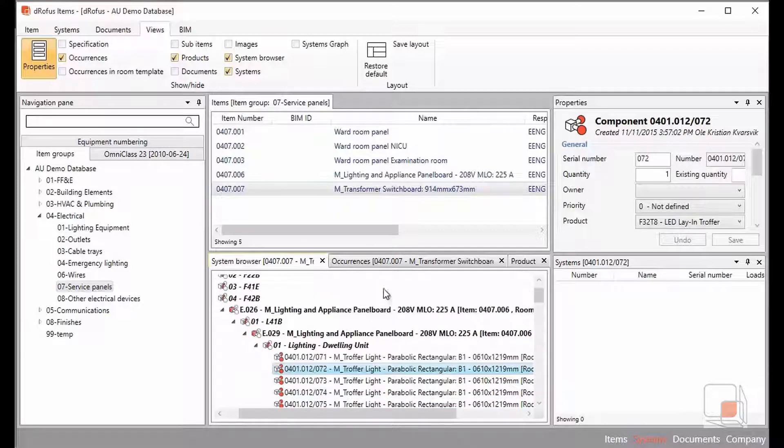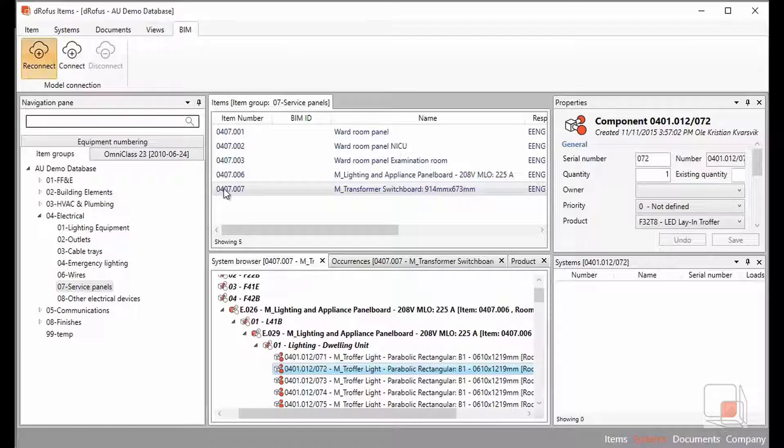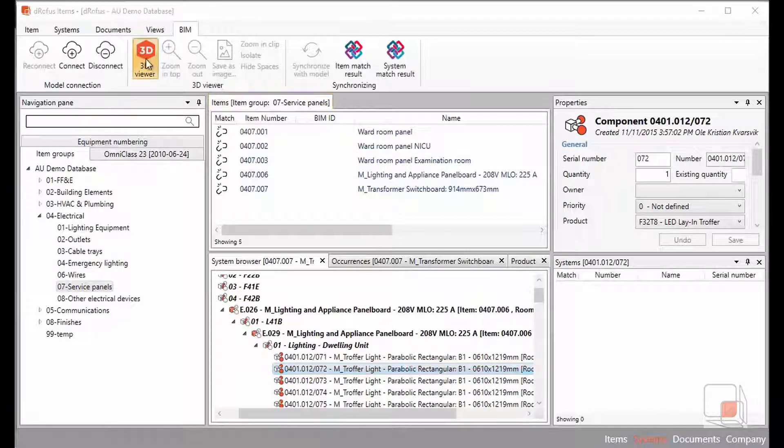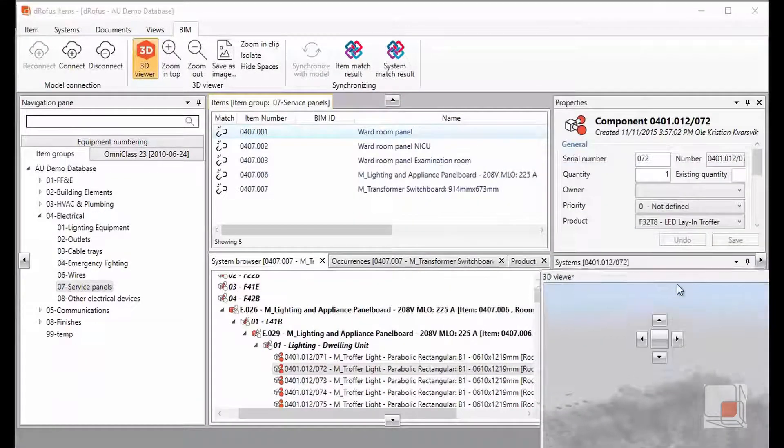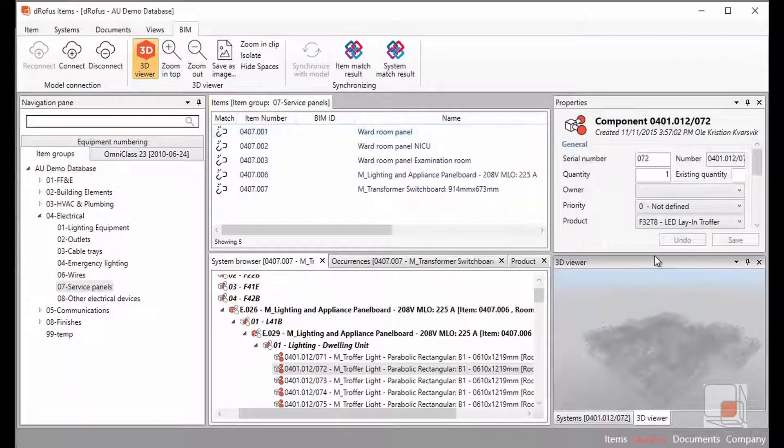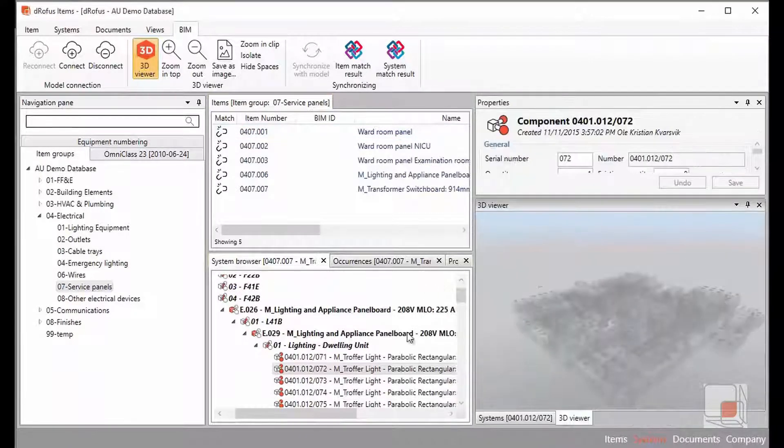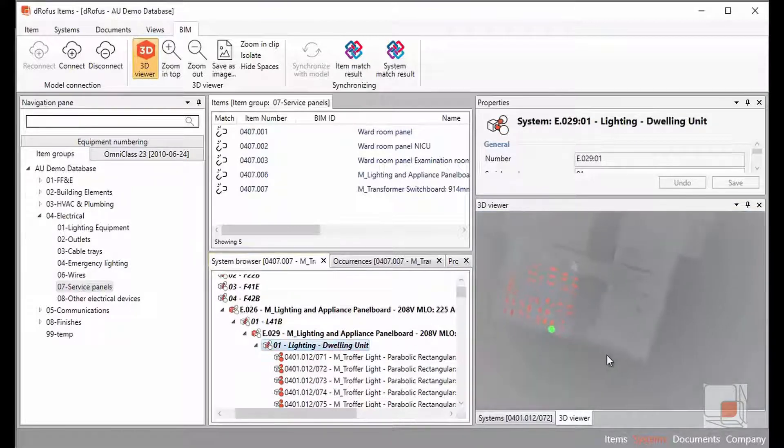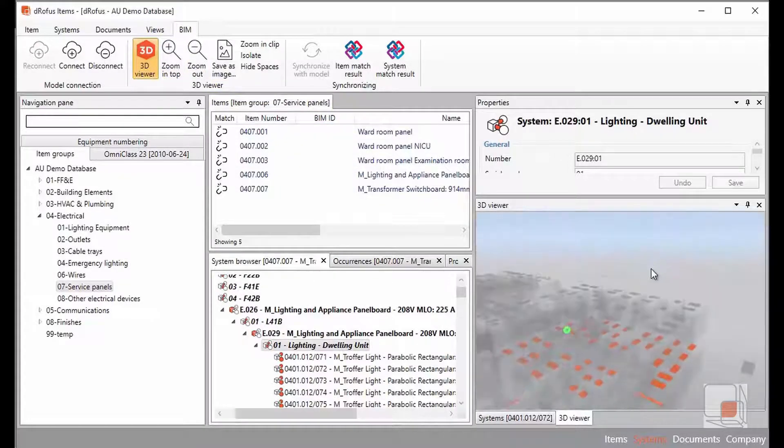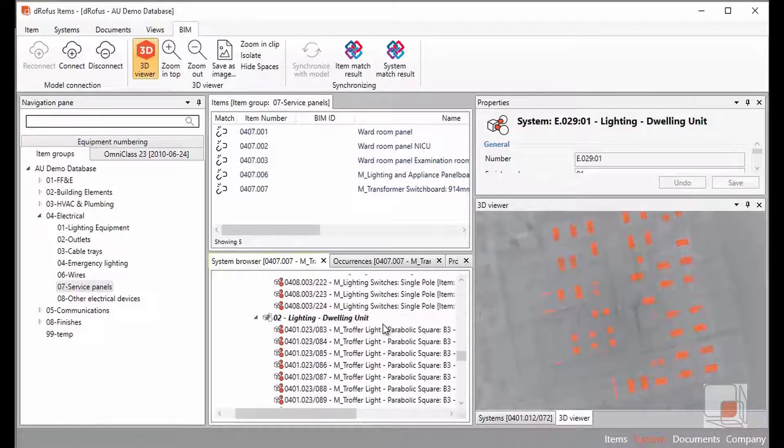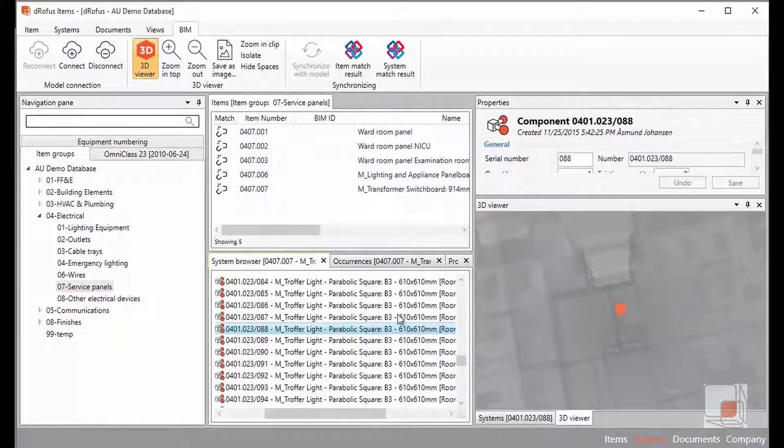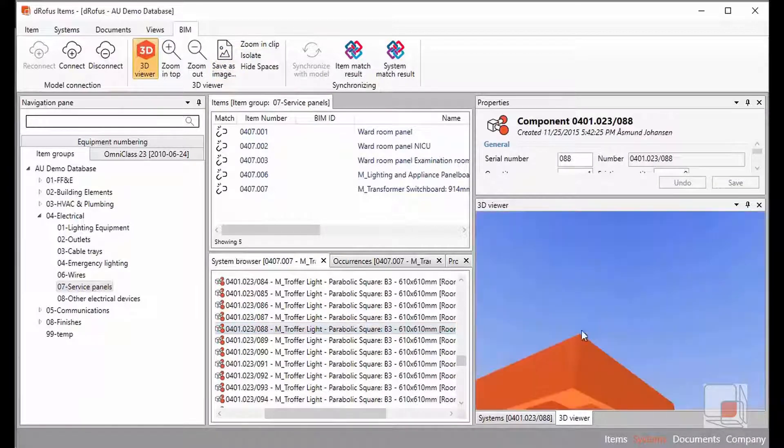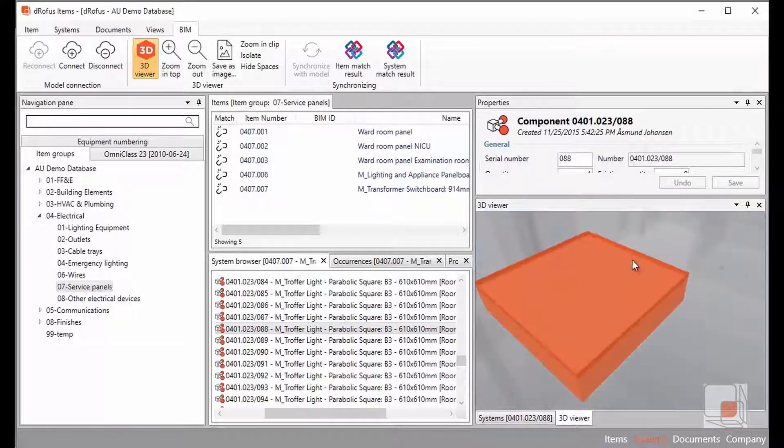This adds additional power because now that I have that inside of my dRofus environment, I could connect this to a 3D model that I've imported as well. I could take my Revit model and import it as an IFC and view that system component and that system overall integration with my IFC model. By selecting the light dwelling unit, it's highlighting all of those troffer lights that are associated to that system. So as a non-Revit user, I could be in dRofus visualizing the connections associated to these components. I could select individual light fixtures and confirm that they are the right type.